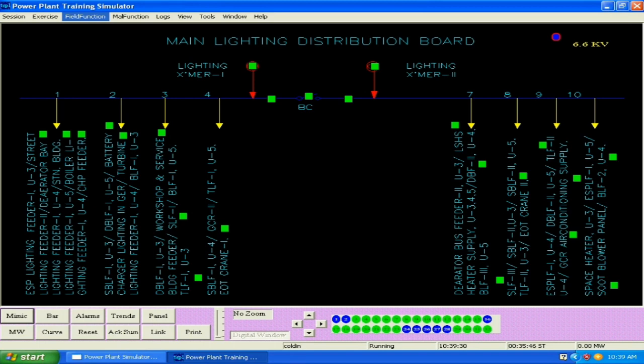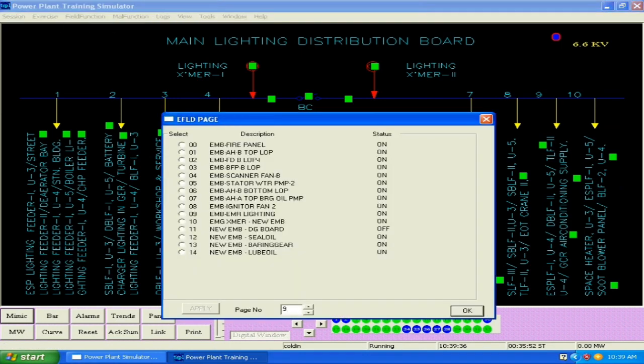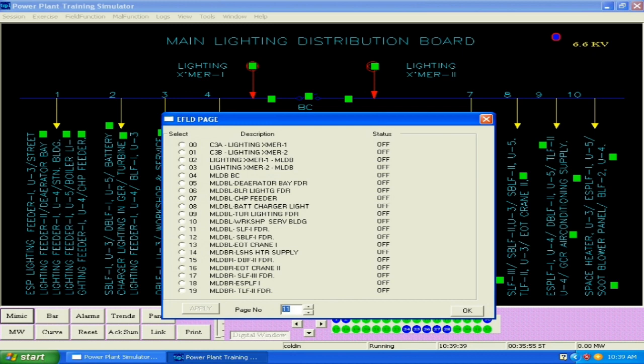Then lastly comes the lighting. So the main lighting distribution board is there, wherein all the switches for lighting and all the supplies for lighting are given. So you have to first, there are two lighting transformers, lighting transformer 1 and lighting transformer 2. So in E-field page number 9, both the lighting transformers are to be charged. So you have to make the breakers on here on C3A and C3B and charge the lighting transformer 1 and 2, and the main lighting distribution board you have to make it on.